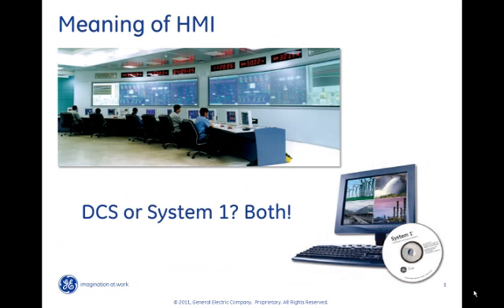While many examples shown later in part two of this presentation may give the impression that condition monitoring is mainly about trending — and as such could be easily implemented in a distributed control system — in general this is not the case. While trending usually gives the earliest warning, determining the severity and exact position of a problem usually requires dynamic data and special condition monitoring software such as System 1. The value of connecting these two systems together is obvious: condition monitoring in simple form is performed 24/7 through DCS, any meaningful alarm will be detected, and a machinery diagnostic service can be asked to diagnose the severity in more detail. Also, machinery operational information from DCS to System 1 — machine loads, speed, and other relevant process information — can be correlated with vibration data to help the machinery analyst do their job better.